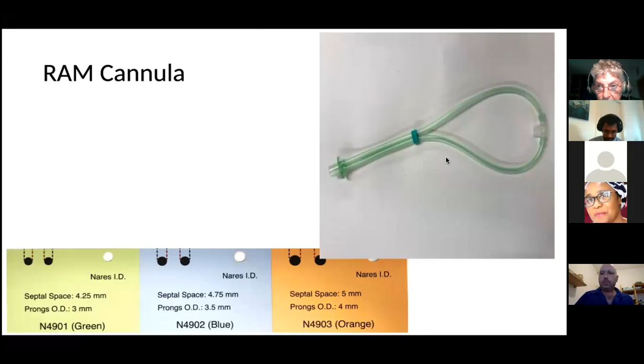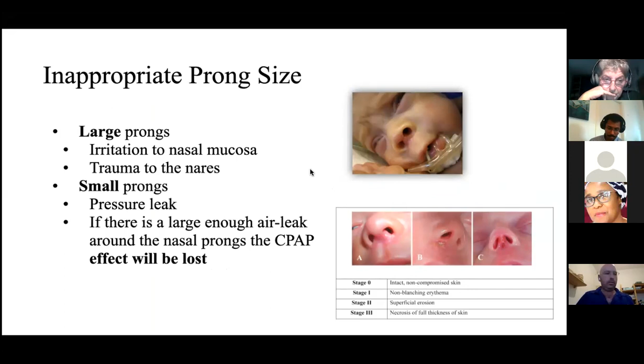We got to the parts that are connected to the patient, either the RAM cannula or the Hudson prongs. It's important that we choose the right cannula or prong size. Too large prongs will cause trauma to the mucosa and the septum, and small prongs will cause pressure leak and the baby will not receive enough CPAP. So the work of the machine won't be as efficient as it could be.